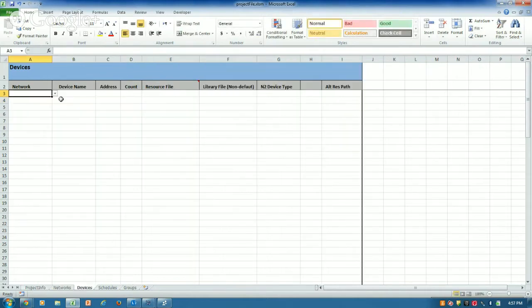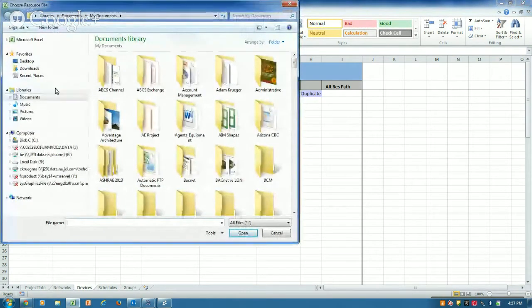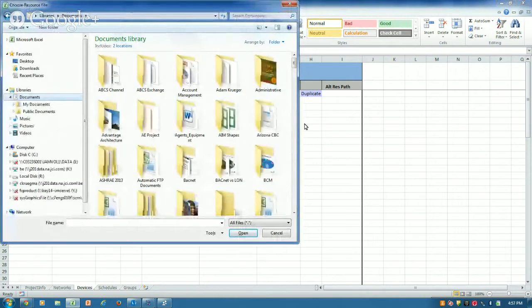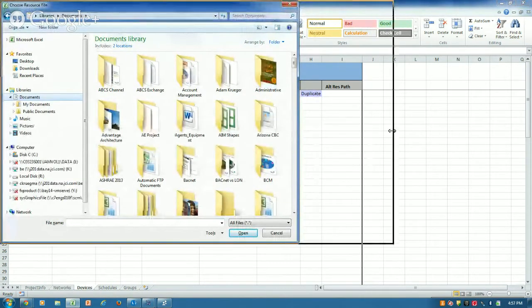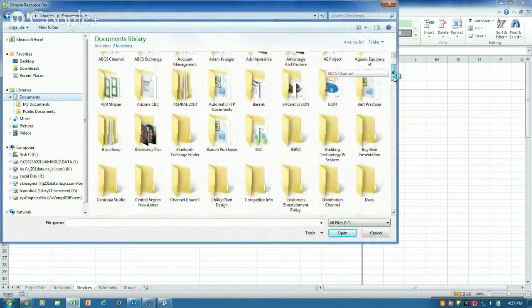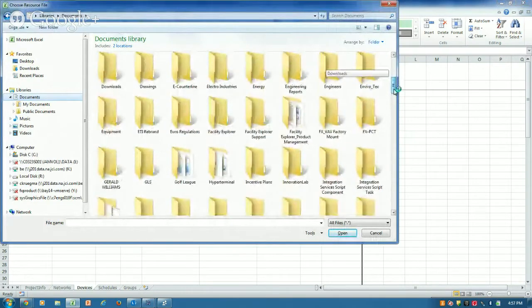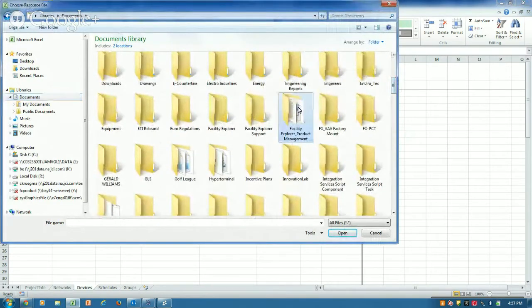Now I'm going to add some devices to those networks. I'll go to my BACnet MSTP network and add some devices. This is the MSTP address, how many of those devices I have, and then I click and navigate to my resource file. When you create an application with Johnson Controls PCT tool, it ends up in a CAF file, or controller automation file, and you can save those.